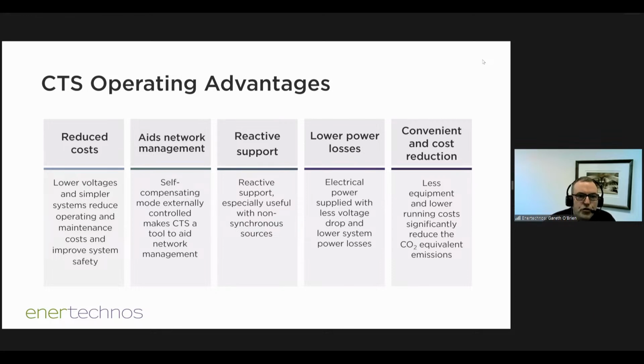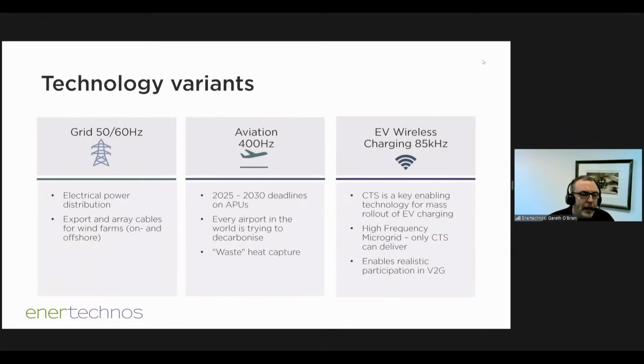Supplied at a lower voltage drop means you're pulling less current. Ultimately, that's where your losses improvement comes from, since losses scale with the square of the current. All of that adds up to a lower carbon footprint.